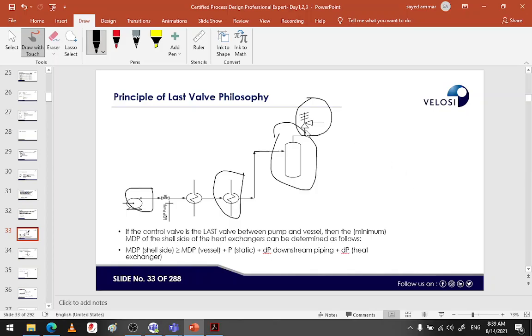Why? Because simply we can install a pressure safety valve here and another pressure safety valve here, and we will be safe. You know the cost of a 4-inch pressure safety valve? It's almost $10,000 US. That's why we are trying to protect all this by the last valve philosophy.